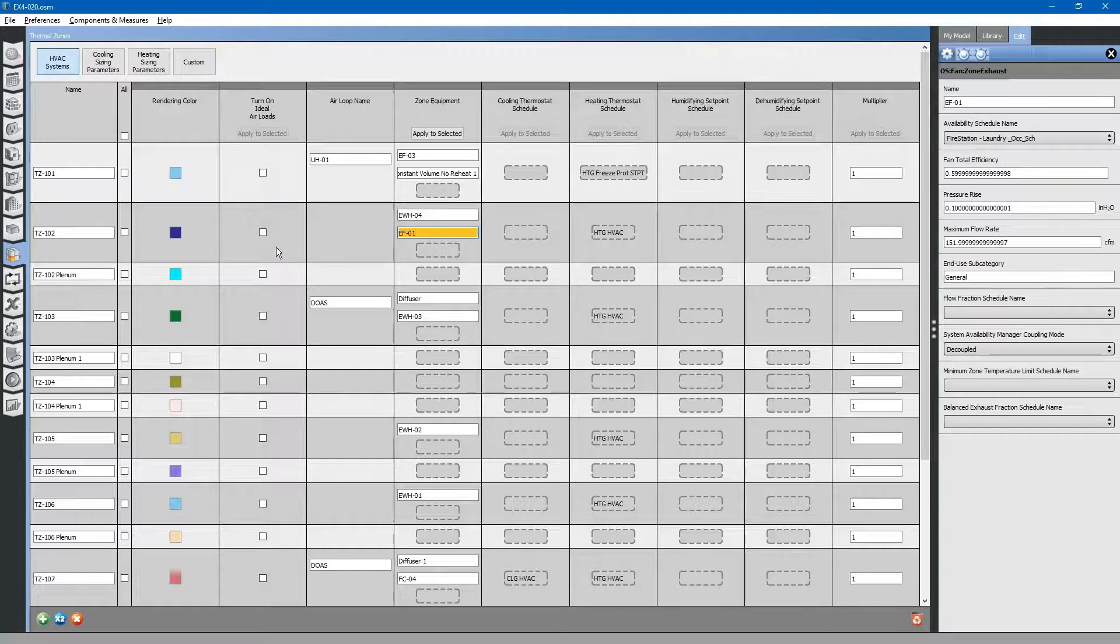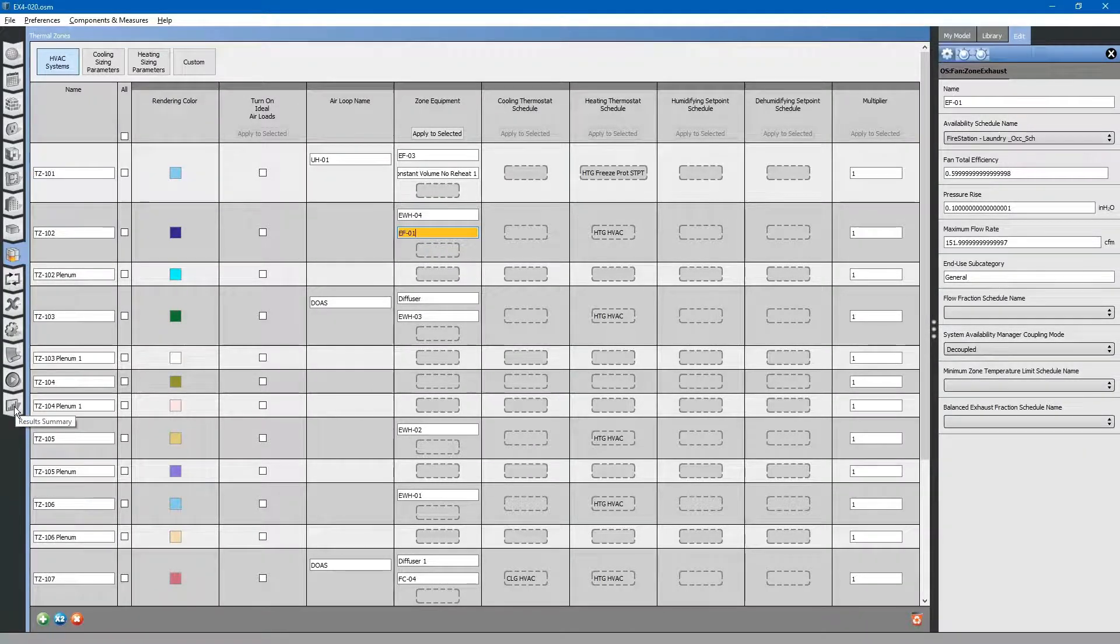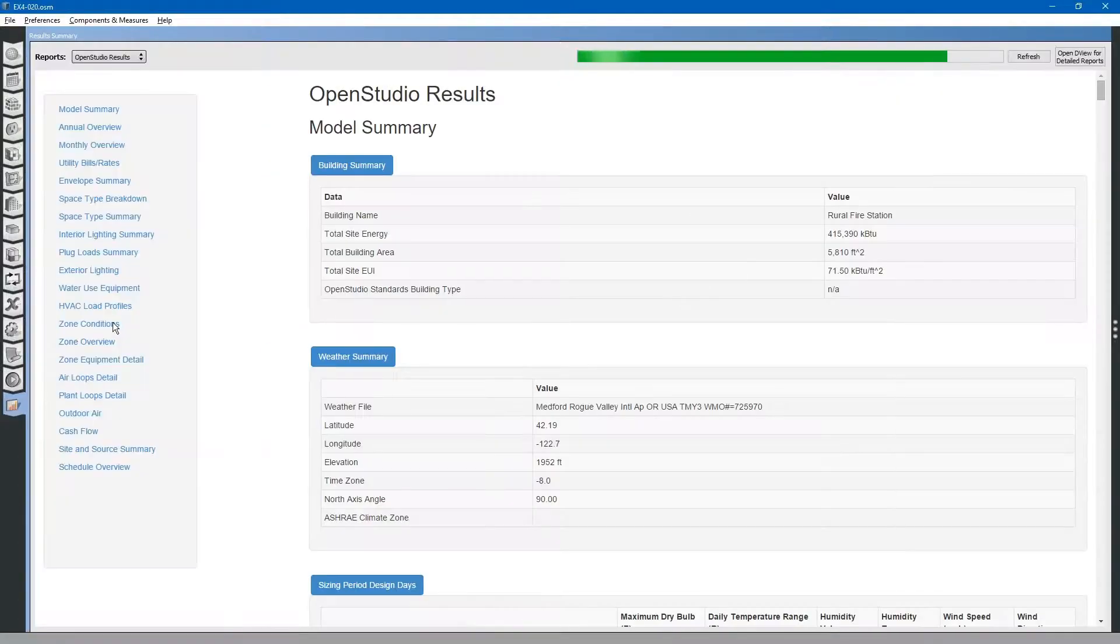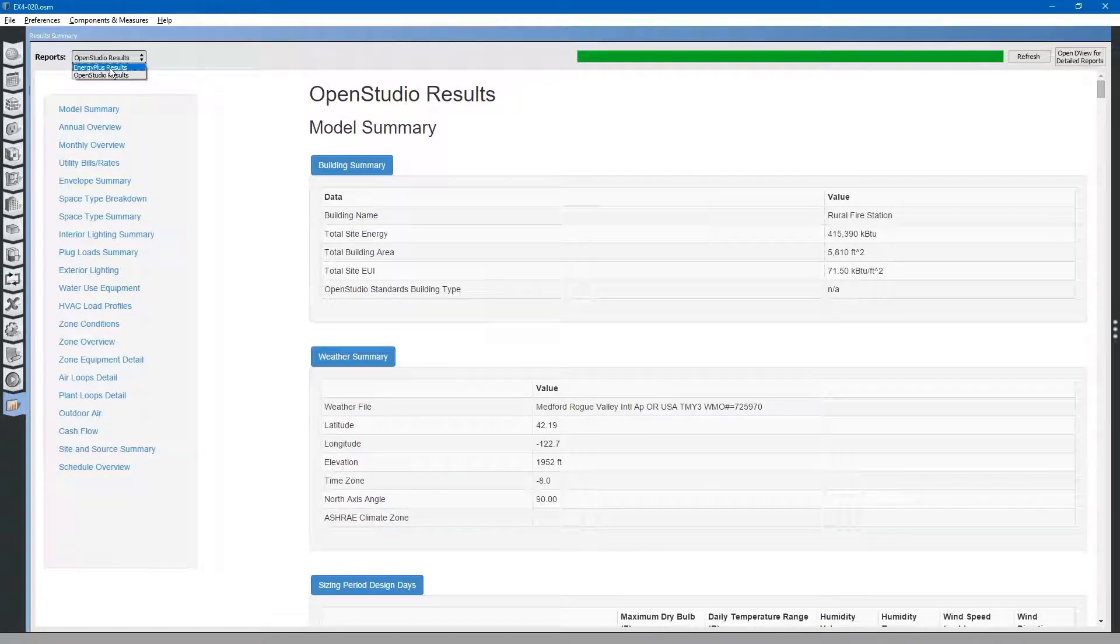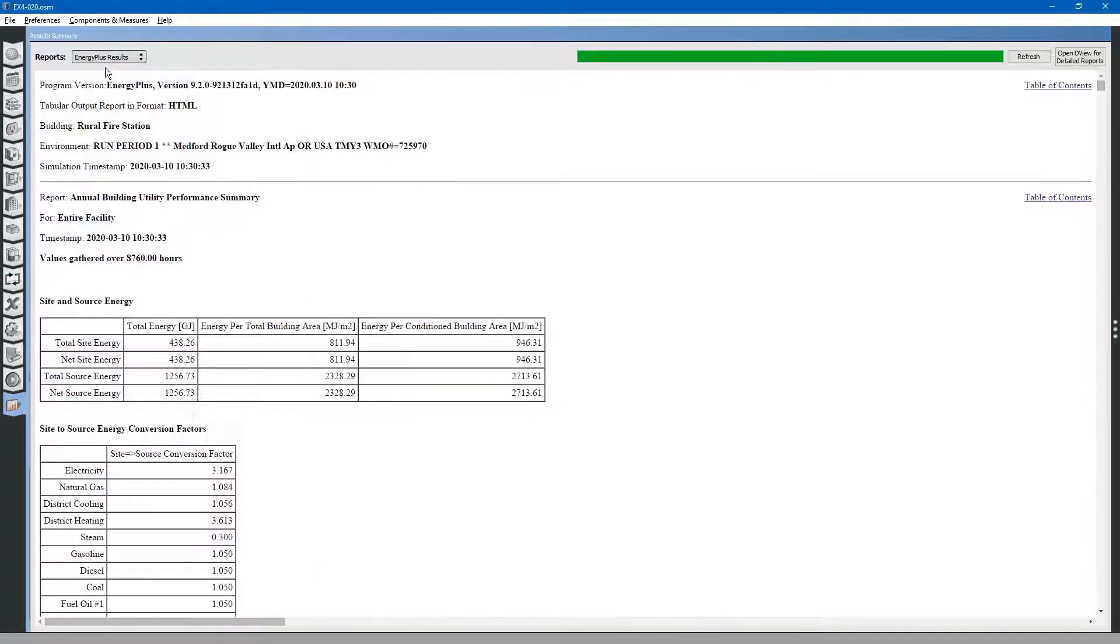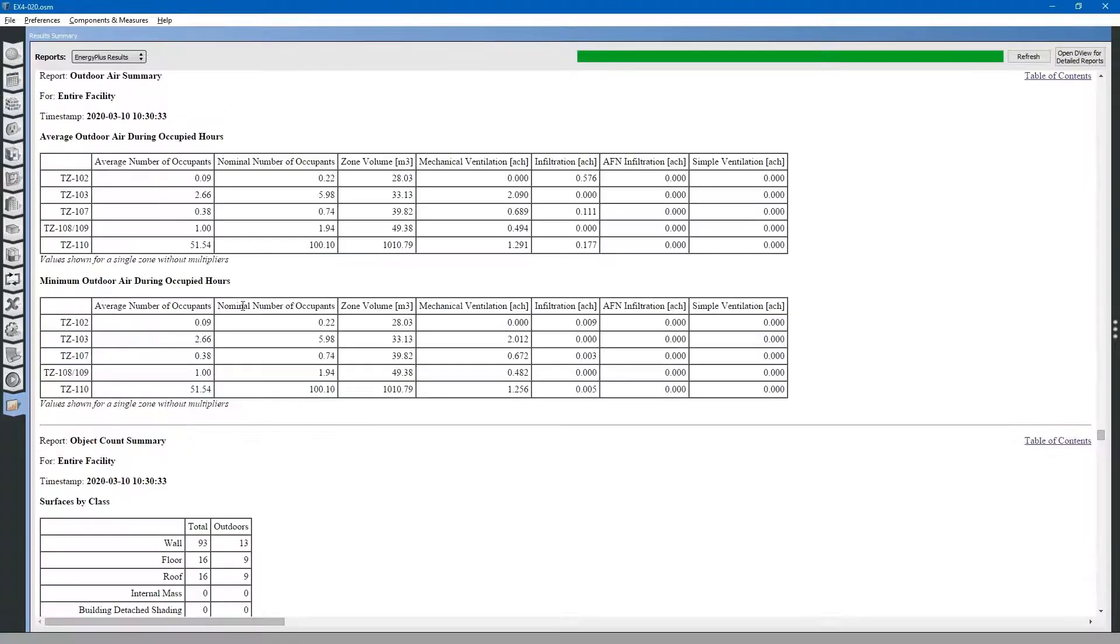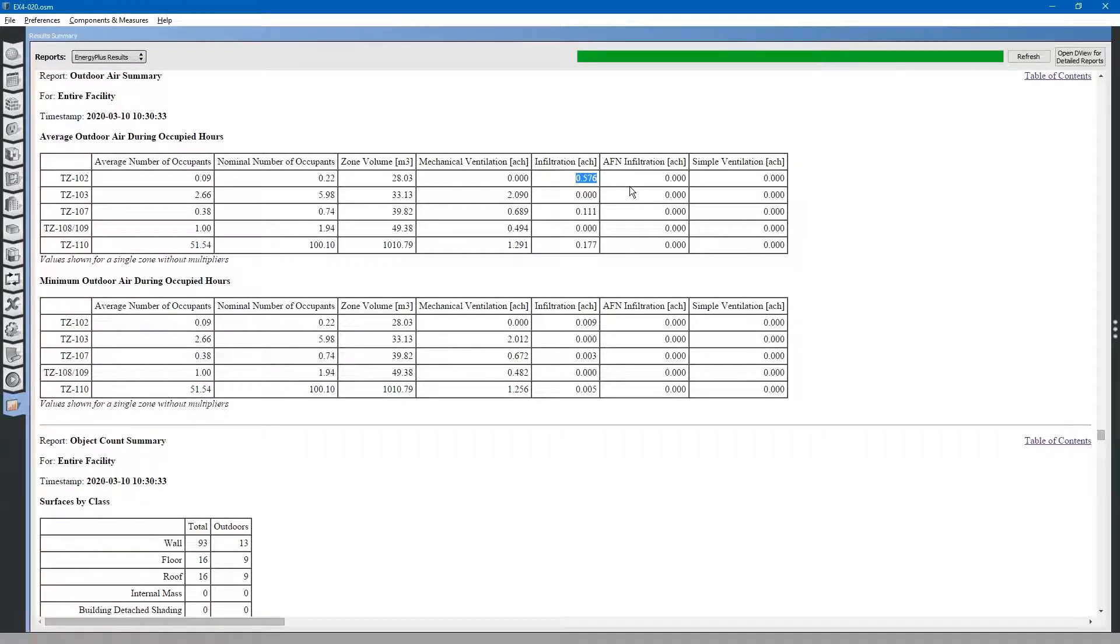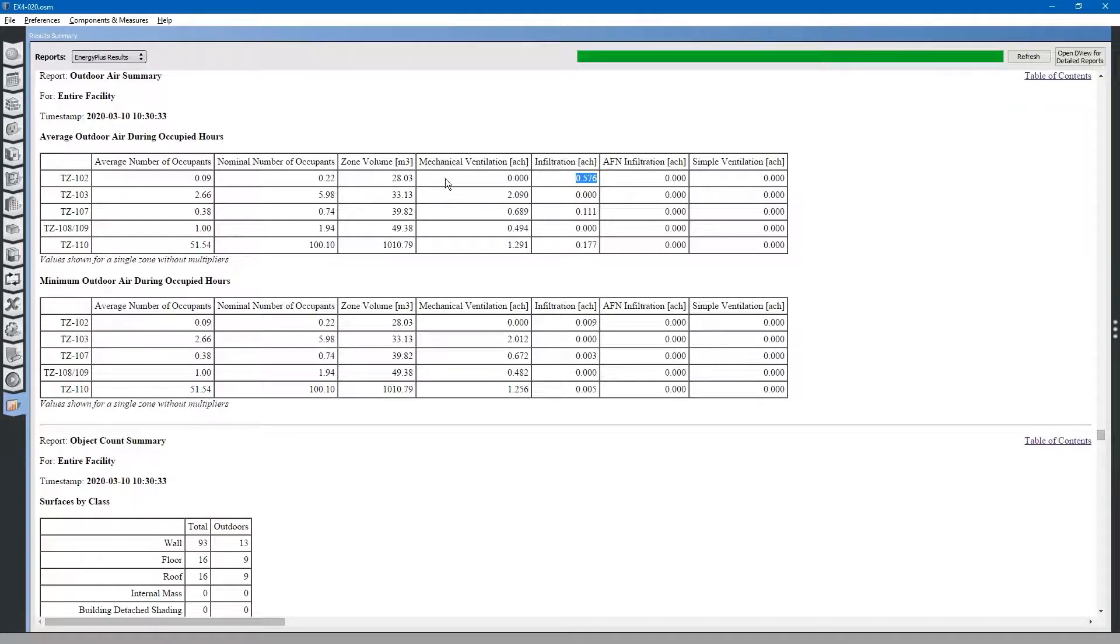Just for curiosity, let's take a look at what the infiltration is for that room. If we go to the EnergyPlus results, table of contents, and outdoor air summary, we can look at the infiltration rate for this room. Let's take a look at the exhaust fan, which is approximately 10 CFM. That exhaust fan is just exhausting 10 CFM.